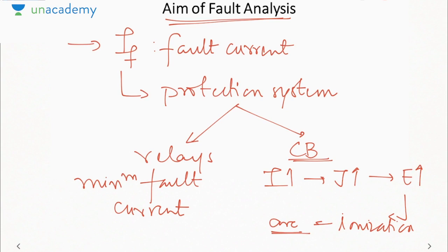Now higher the current, more dangerous is the arc. So that is why we need to know the maximum fault current, so that we know how dangerous the arc can be, or what is the maximum arc intensity that I have to extinguish. That is why circuit breakers are designed based on maximum fault current. Okay, got the reason? Because with the maximum fault current, the arc will be the most severe, and we need to devise a method to extinguish that arc, which we can only do if we have an estimate of maximum fault current.